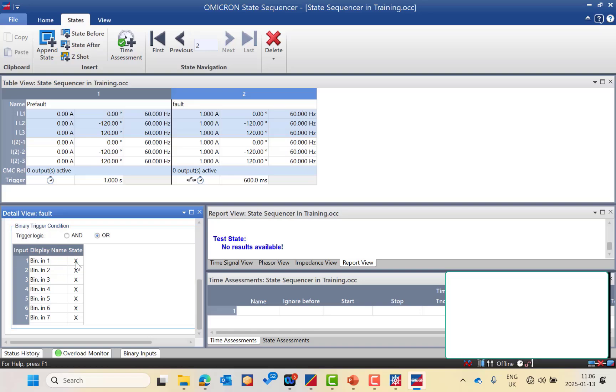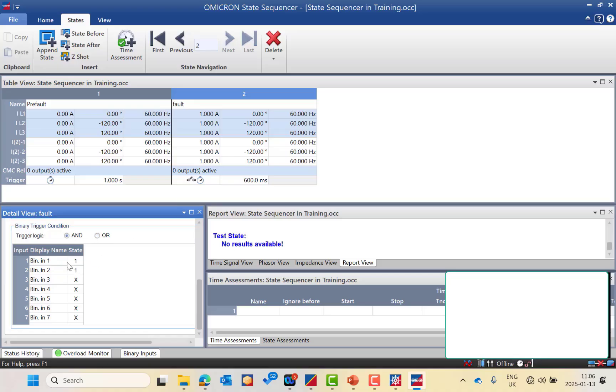The change of state from 0 to 1 is very important for accurate assessment of your test results. If you are using one contact as both start and trip at the same time, you can set the logic using an AND gate, so once both binary inputs change from 0 to 1, it will assess the trip time and give you the assessment.